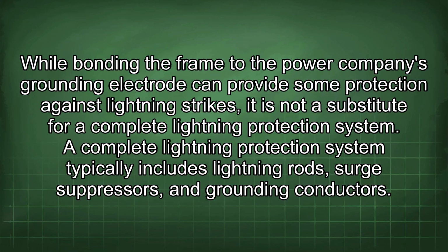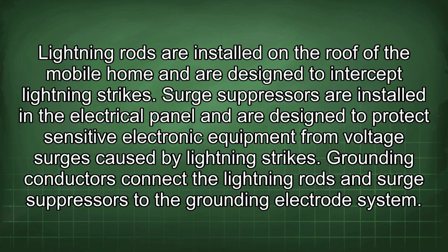A complete lightning protection system typically includes lightning rods, surge suppressors, and grounding conductors. Lightning rods are installed on the roof of the mobile home and are designed to intercept lightning strikes. Surge suppressors are installed in the electrical panel and are designed to protect sensitive electronic equipment from voltage surges caused by lightning strikes. Grounding conductors connect the lightning rods and surge suppressors to the grounding electrode system.